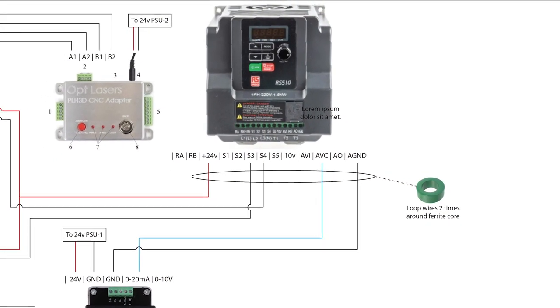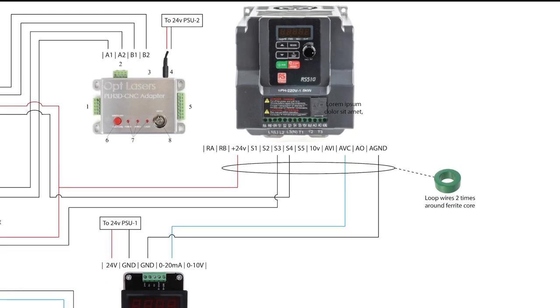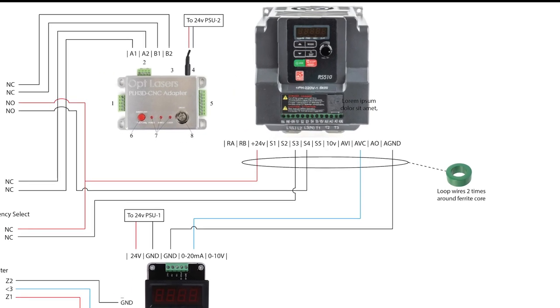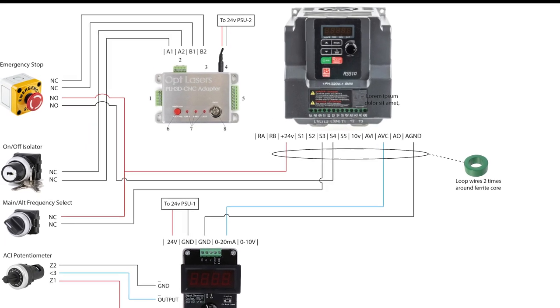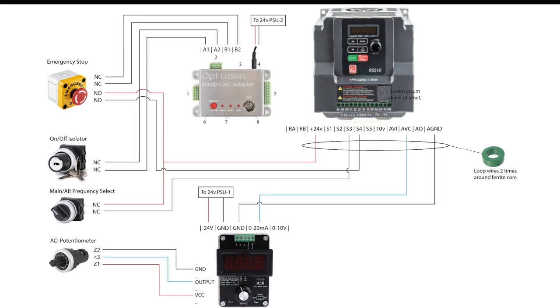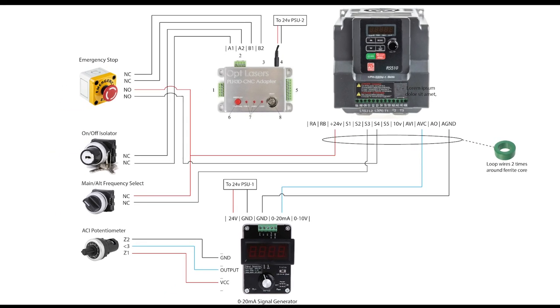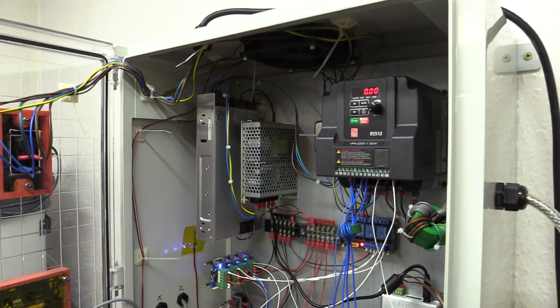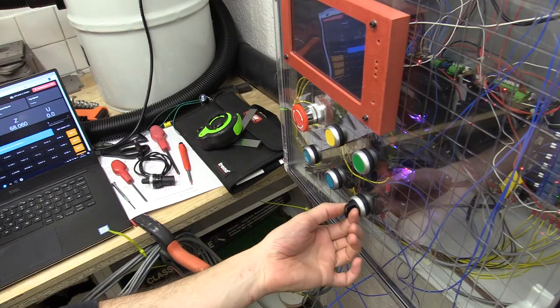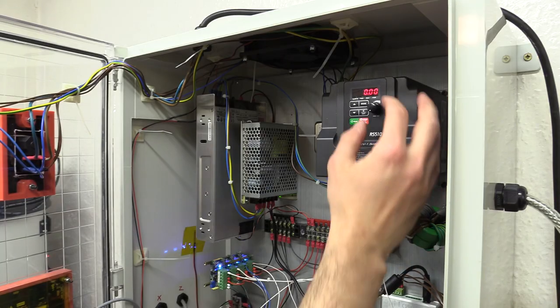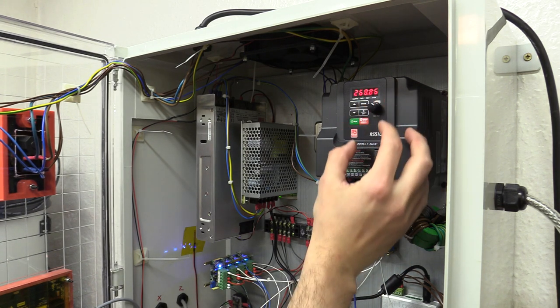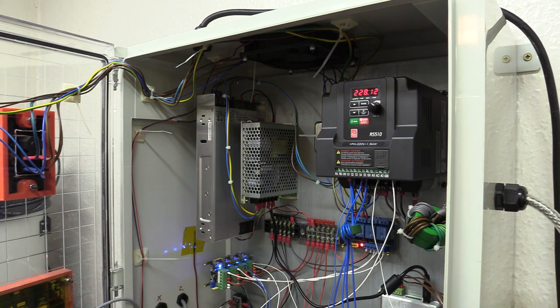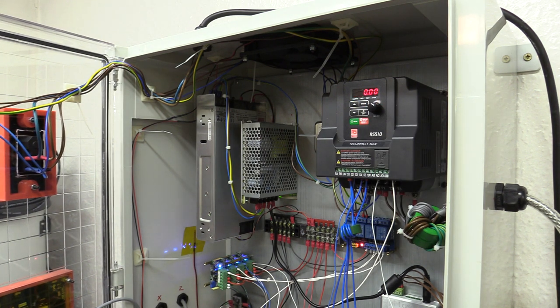I then set the S3 input to 13 main forward slash alternative frequency command select, which is wired to a latching two position selector switch. While option 00-07 is set to 0 main or alternative frequency, one switch position selects the main input mode via 00-05 which is option 2 external AVI analogue signal input. And the second position for now utilises option 1 potentiometer on keypad. But I'm planning to install a signal generator and use option 3 external ACI analogue signal input at a future date. At the moment if I try and move the potentiometer it doesn't do anything and then if I flip the switch you can see I can set the speed based on this and it ignores the input coming from the controller back to zero.